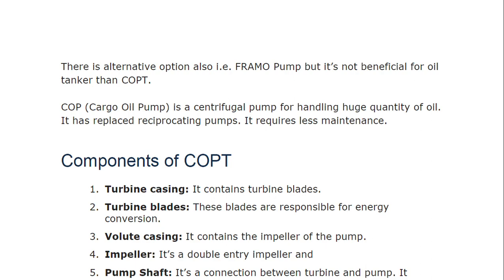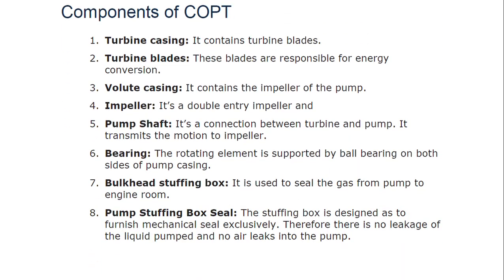The Cargo Oil Pump is a centrifugal pump for handling huge quantities of oil. It has replaced the reciprocating pump and requires less maintenance. Components of COPT include: the turbine casing with turbine blades responsible for energy conversion; the volute casing which contains the impeller of the pump; a double entry impeller; and the pump shaft which connects the turbine and pump and transmits motion to the impeller. The rotating element is supported by ball bearings on both sides of the pump casing.